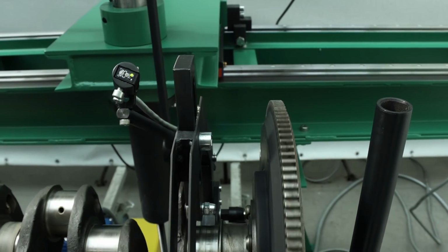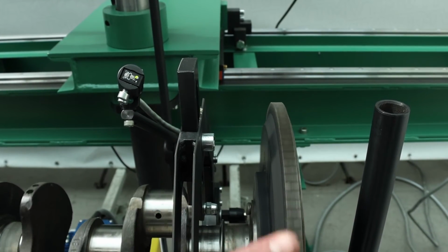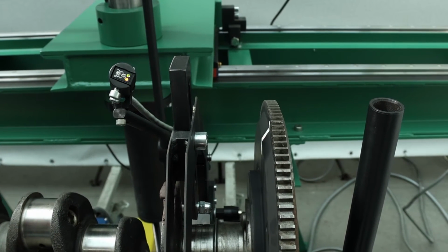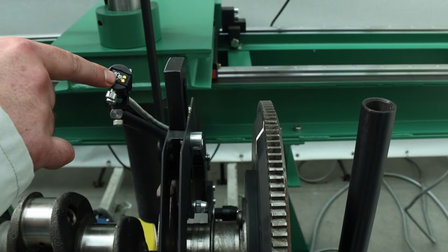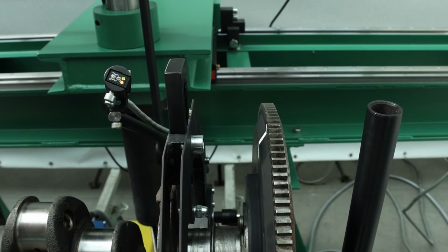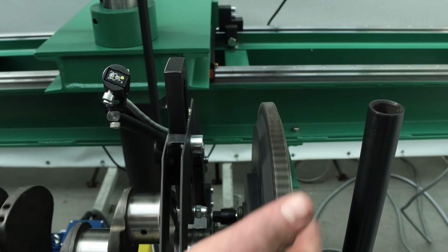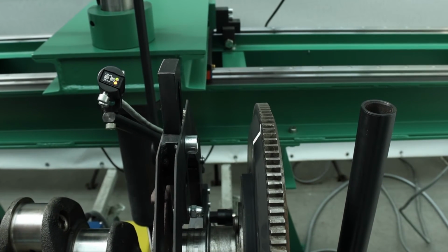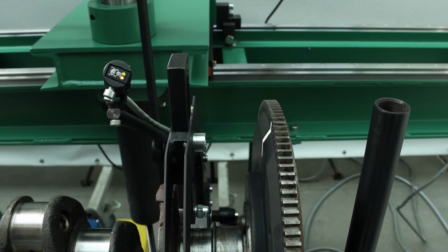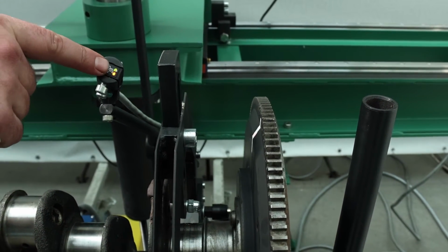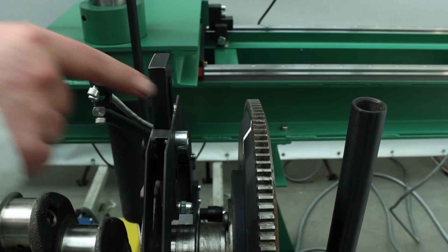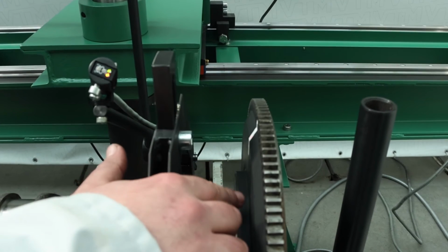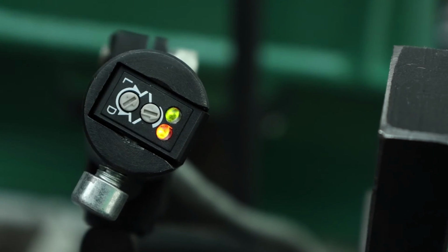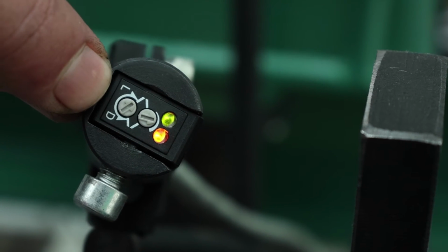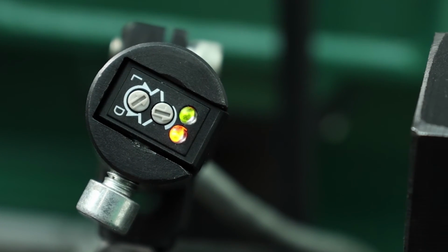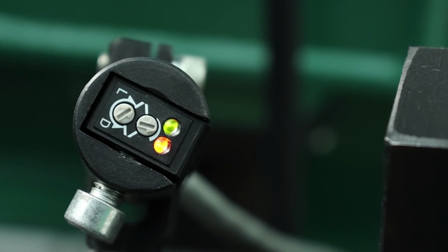After that, we make one complete revolution of the rotor, and see that there are no false alarms. If there are false alarms, we can reduce the sensitivity a little bit. We can turn it a little bit towards the minimum, and then we turn it again and make another full revolution. If there are still false alarms, you can change the angle of the sensor, either the sensor distance or move to a different rotor plane, either up or down. The letter L is light and the letter D is dark. And in this case, we have a light marking, so the potentiometer looks towards the letter L.